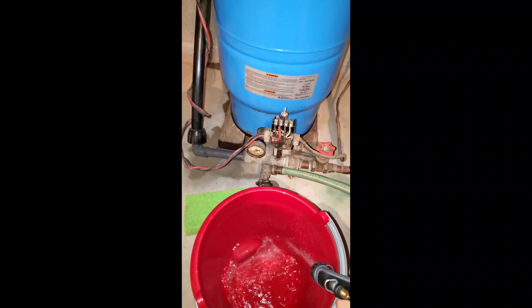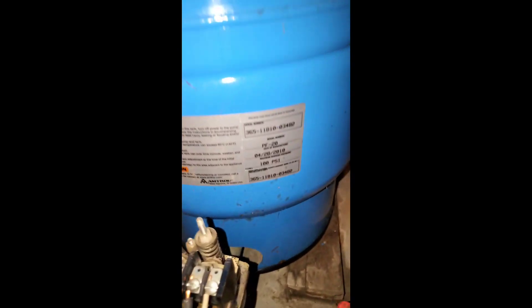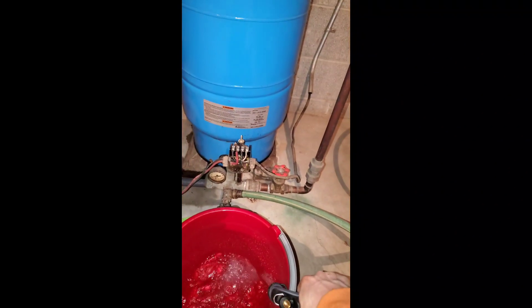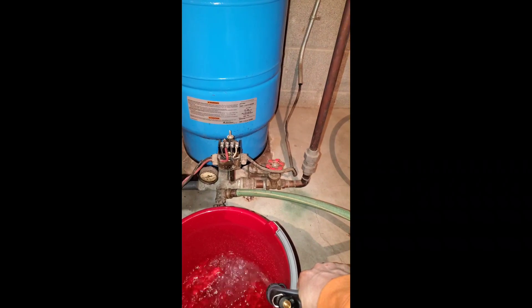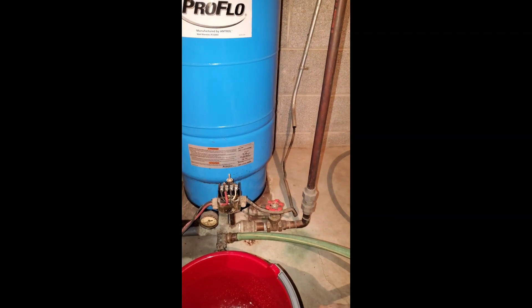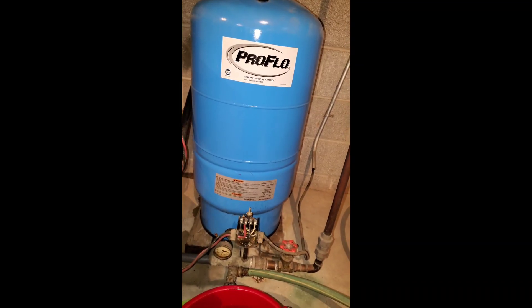Still draining the system down. I found the light — much better. We have an old ProFlo; date code says 2010, so almost 10 years out of it. It's probably waterlogged too. Connections look clean — I'll check them, but I don't see any issues with anything in the system.